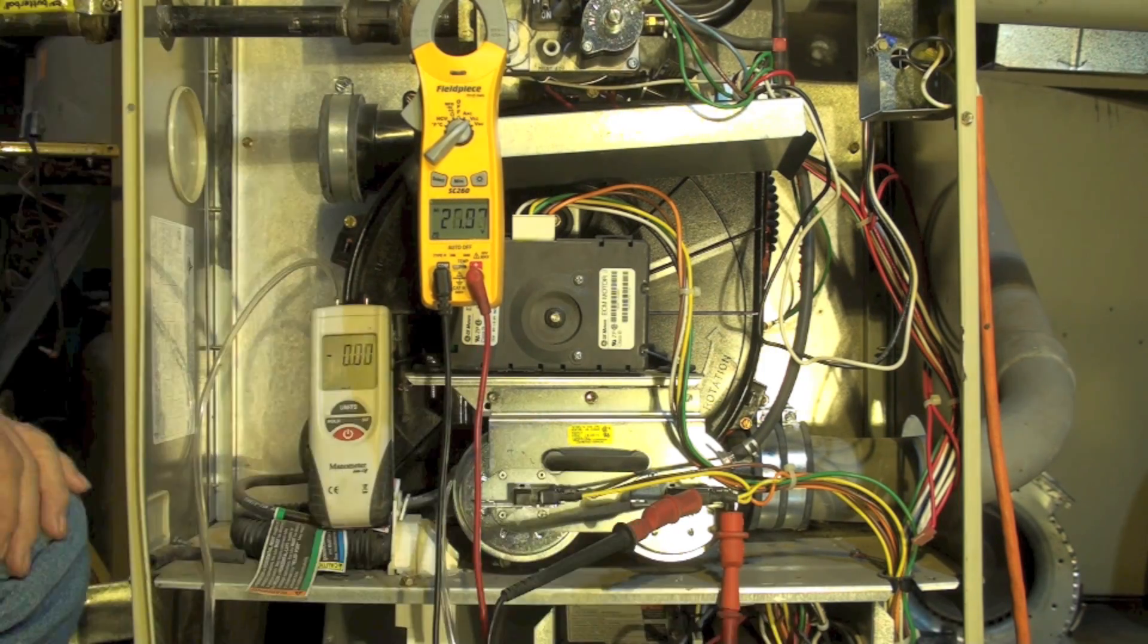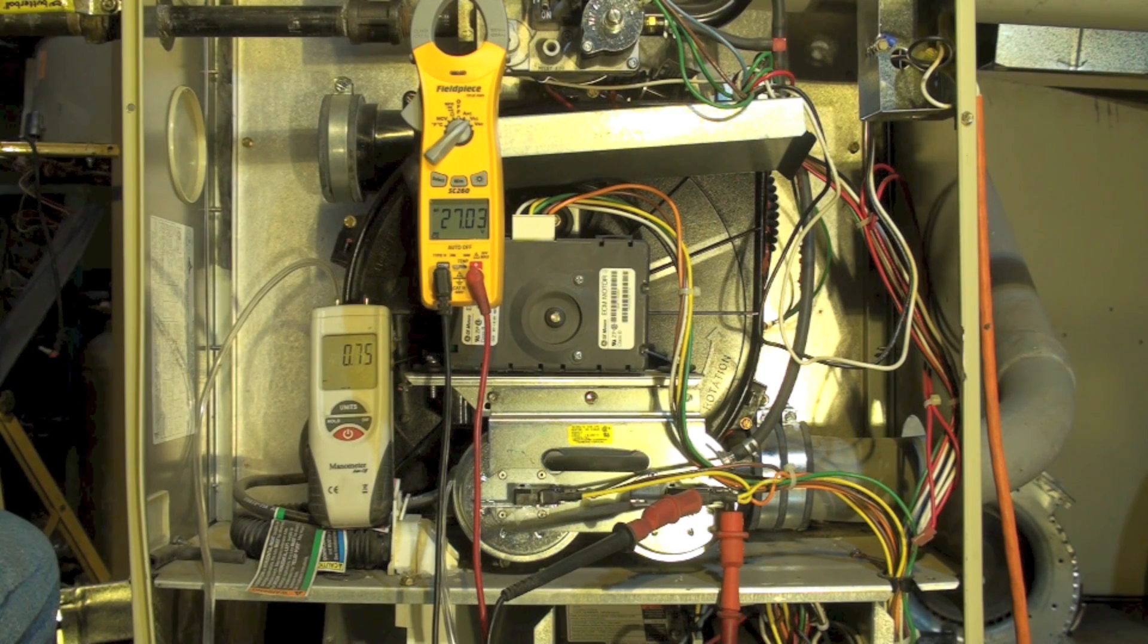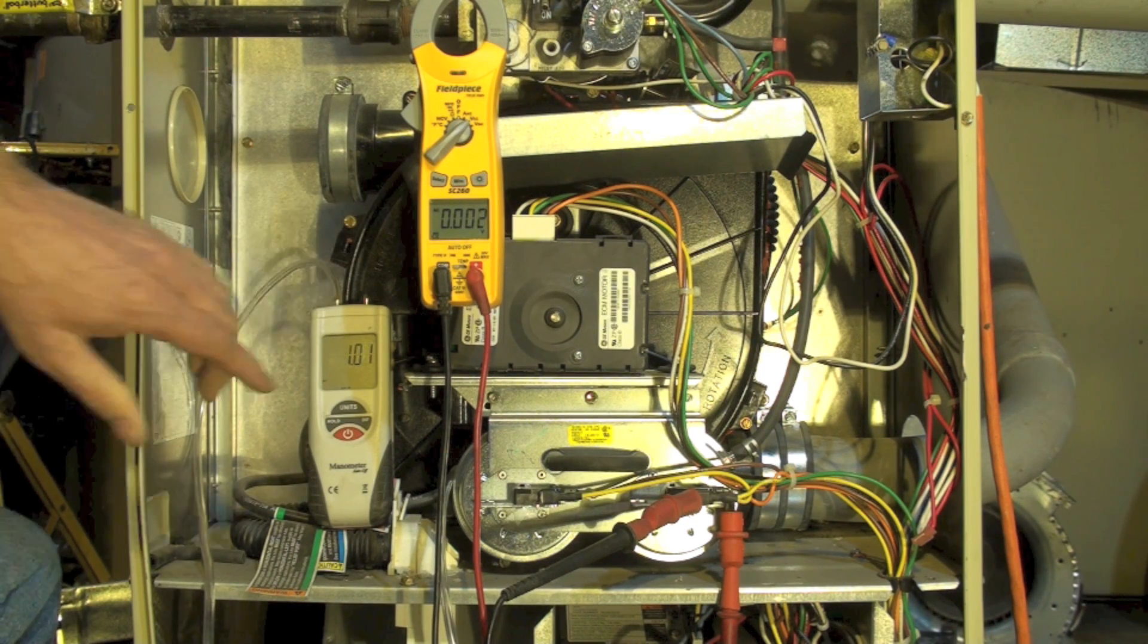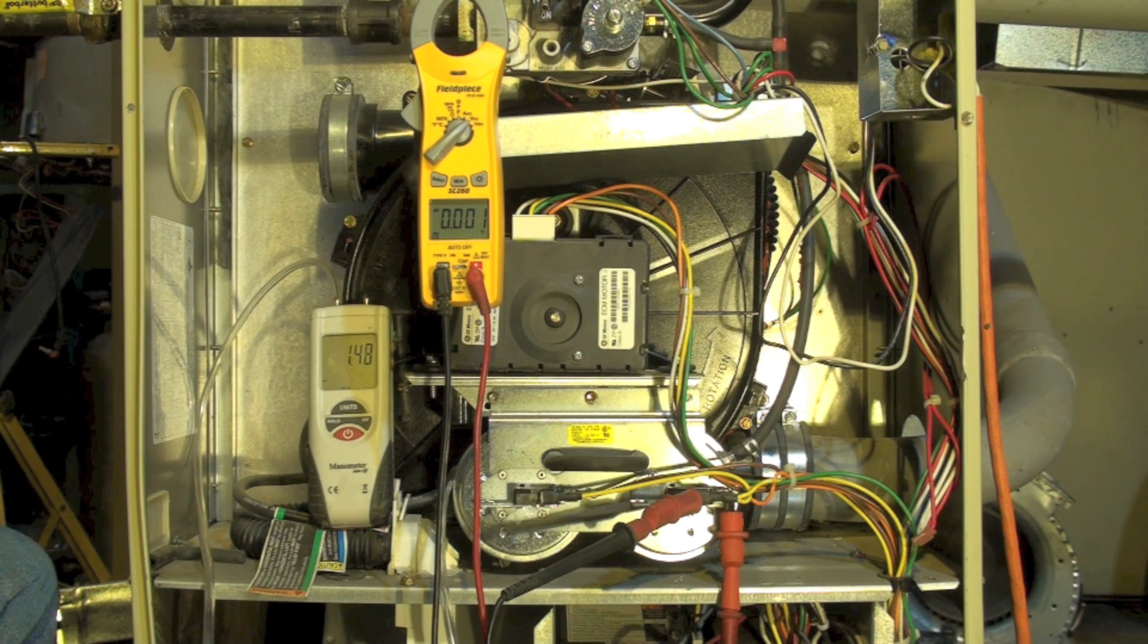Okay, it's on. Notice we have our pressure switch open. Now it's closed. It was a little below one, it was actually about point seven eight or nine or something like that. Okay, now it's going to go through the trial for ignition. It'll warm up the hot surface igniter and then it's going to light the burner.